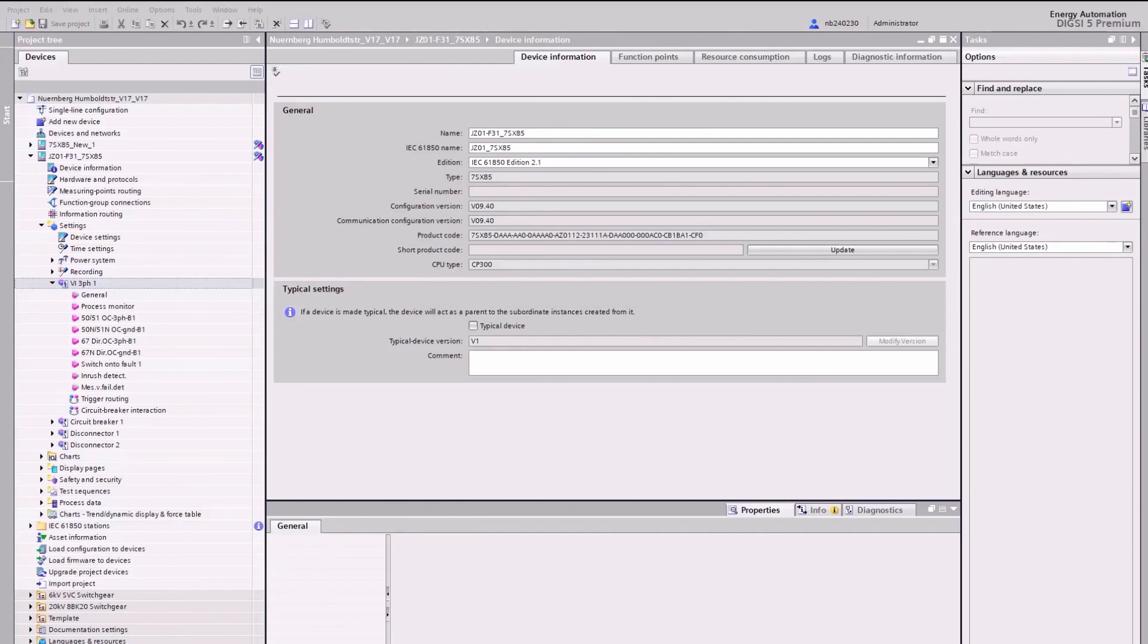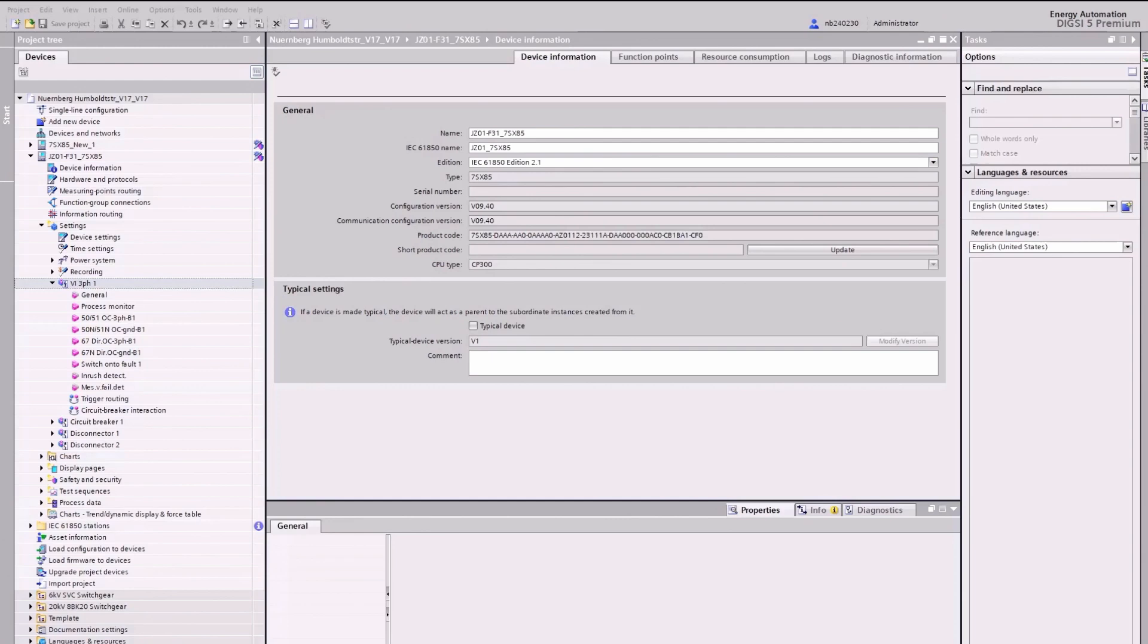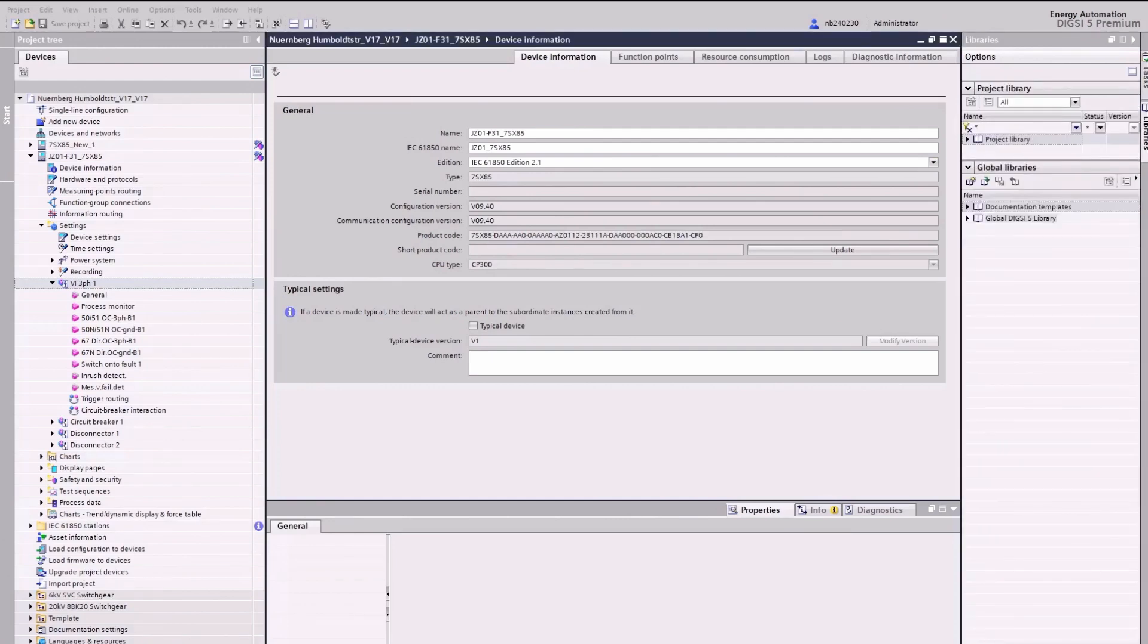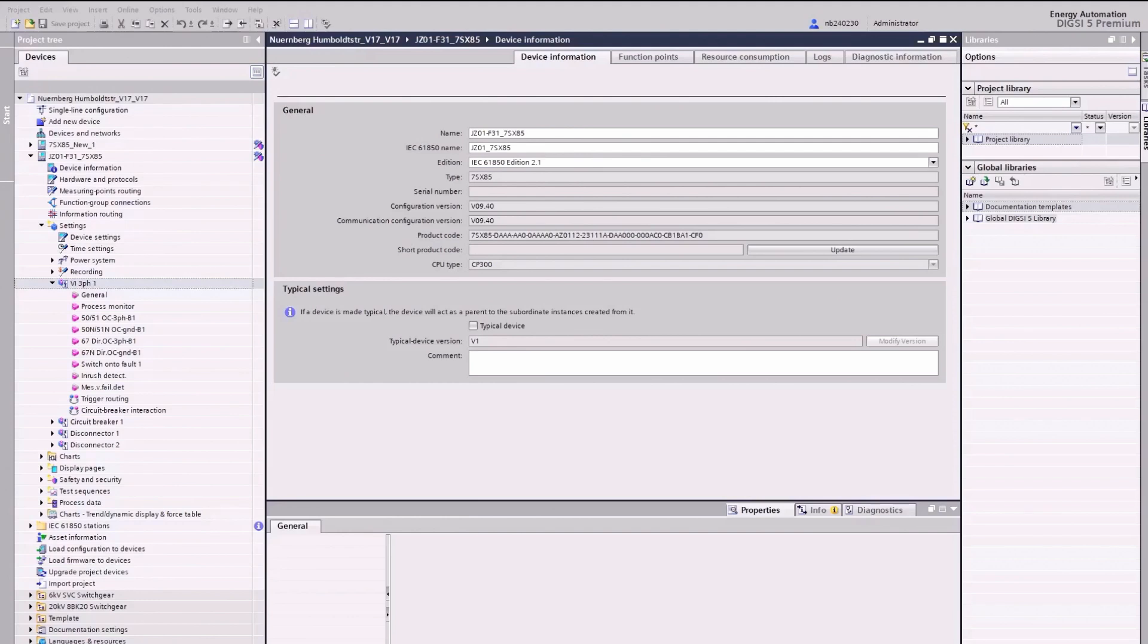Next, we check whether the protection functions embedded in the function group meet our requirements. Superfluous functions can be removed and missing functions can be added from the global library. In our case, the directional overcurrent functions 67 and 67 neutral can be deleted, which saves function points.